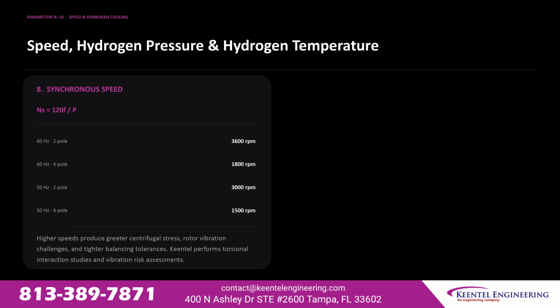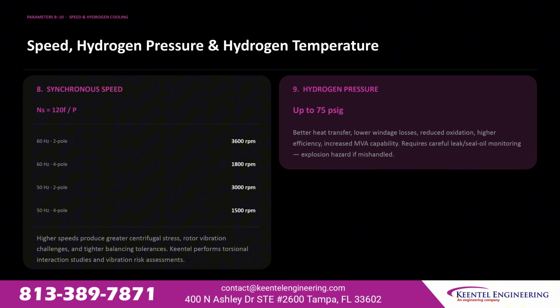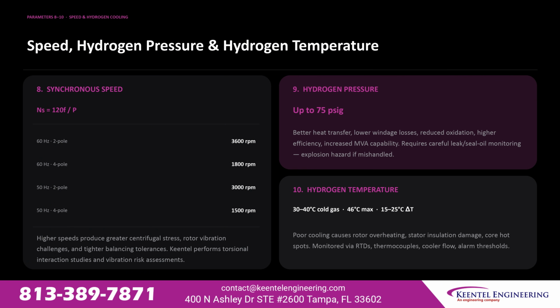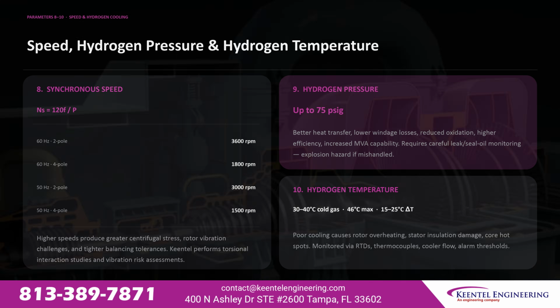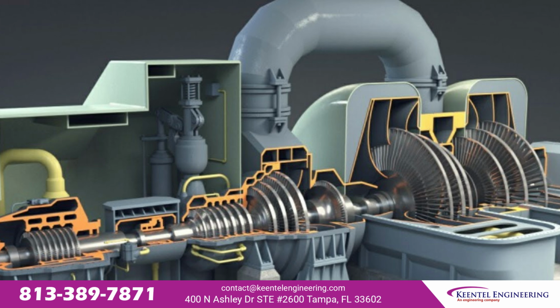At 60 Hz, 2 pole machines run 3,600 revolutions per minute and 4 pole machines run 1,800 revolutions per minute. At 50 Hz, 2 pole runs 3,000 revolutions per minute and 4 pole runs 1,500 revolutions per minute. Higher speeds increase centrifugal stress and tighten balancing tolerances. Hydrogen pressure up to 75 pounds per square inch gauge improves heat transfer, reduces windage losses, and increases MVA capability, but requires careful leak and seal oil monitoring since mishandling presents an explosion hazard. Hydrogen temperature typically runs 30 to 40 degrees Celsius cold gas with a 46 degree maximum and a 15 to 25 degree differential. Poor cooling causes rotor overheating and stator insulation damage, monitored via RTDs and thermocouples.